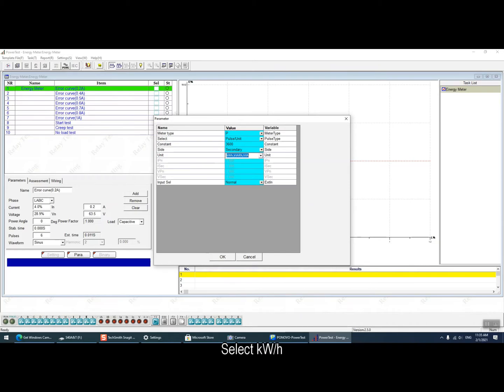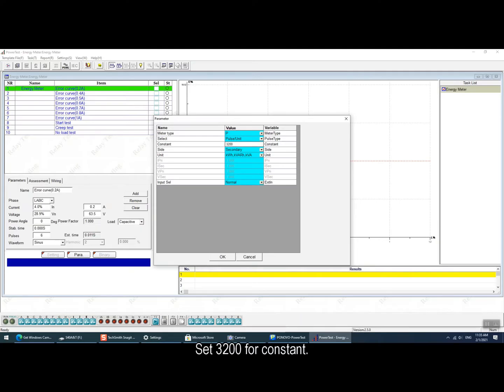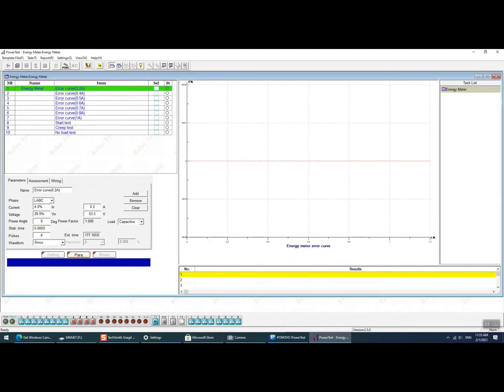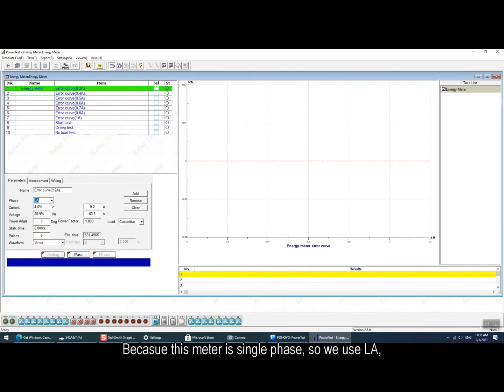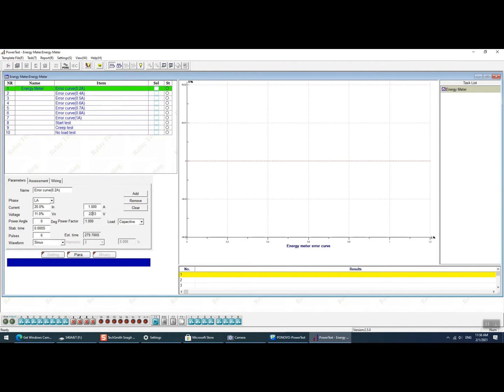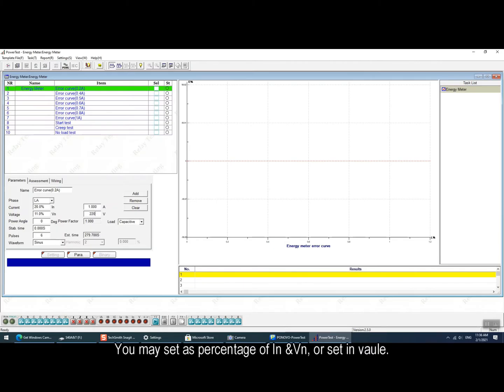Select kWh. Set 3200 for constant. Then set the phase, because this meter is single phase so we use LA. Then set the testing current and voltage. And you may set as percentage of IN and VN or set in value.